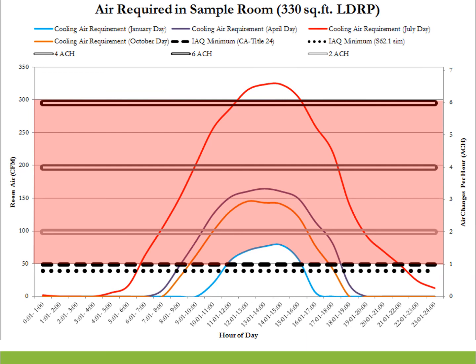Again, 90% of US hospitals have central air systems with terminal reheat. So all that air we put into the room goes through a central system, moved by a fan, then it gets cooled and reheated at the end. If you think about this over-ventilation and multiply it times every patient room in the building or in the country, you can really start to see why our energy use is so high.